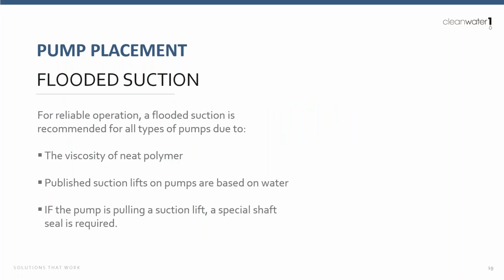So regardless of what pump we're using, these pumps require flooded suction with neat polymer. And that's due to the viscosity of neat polymer itself. The published suction lifts on these pumps are based on water. So, even though you can get a 2.5-foot suction lift with a progressive cavity pump, that's based on water. So we always want to have the polymer supply either at or above the suction of that pump. And then if the pump is to pull a suction, if it's absolutely required, a special shaft seal is required. It's really important to avoid this at all costs because it basically makes the pump work a lot harder. And again, maintenance and operational issues can happen. You can burn out stators if you run dry. The motor's working harder. So we really, really recommend flooded suction for reliable operation.